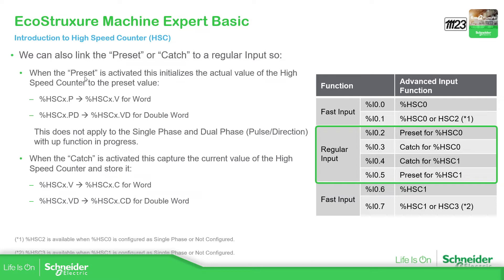The preset will allow you to initialize the high-speed counter to the preset value you have assigned. This doesn't apply to single phase — it just goes to zero, it doesn't go to the preset value. The catch will move the actual value to the .C instance of the high-speed counter you are using. So imagine you want to capture the value for calculations — instead of using the .value directly, you trigger the catch to capture it. Depending on whether you have configured word or double word, there is a different assignation, which we will cover later.